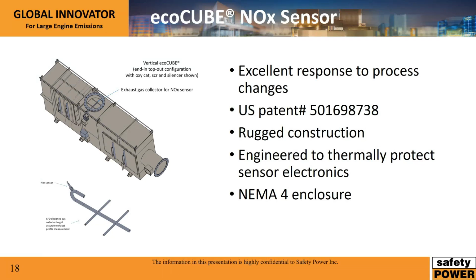More importantly, they have a much quicker response time. Electrochemical type sensors have a response time of at best around 30 seconds, whereas solid-state sensors have a response time in the millisecond range, which is a very key factor for engines that have varying NOx emissions, which is very common as well. This helps us recover very quickly with our reductions.